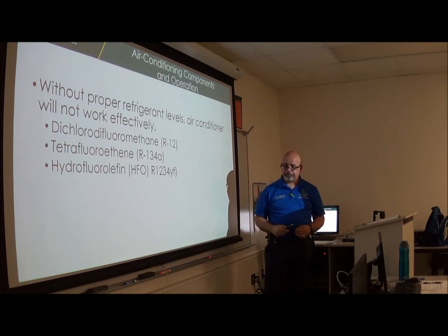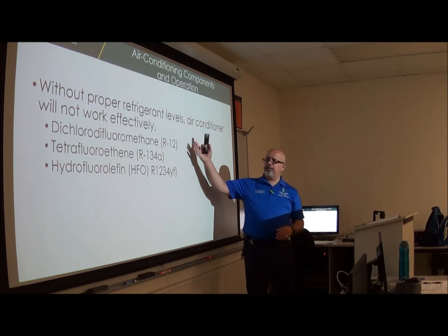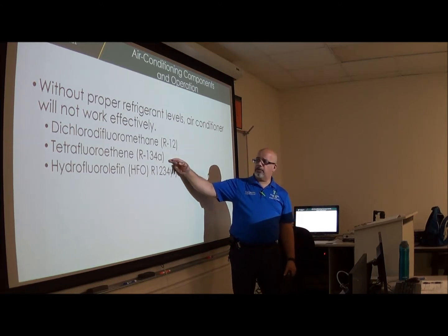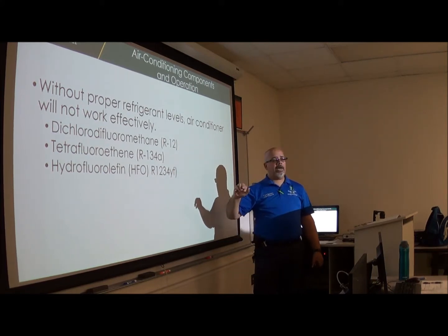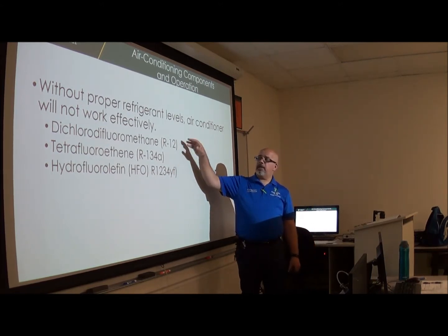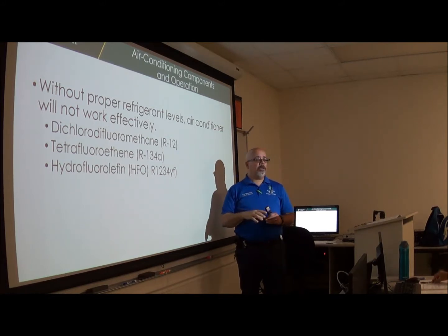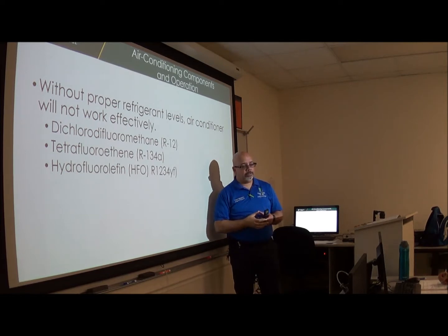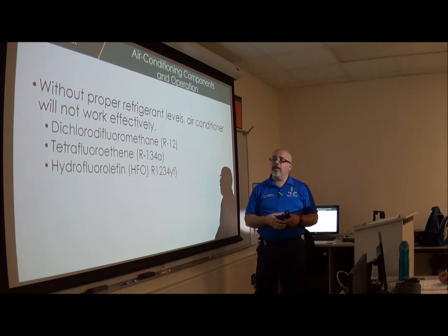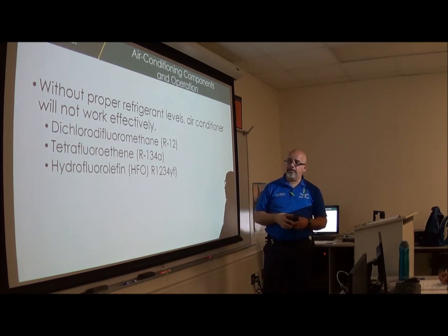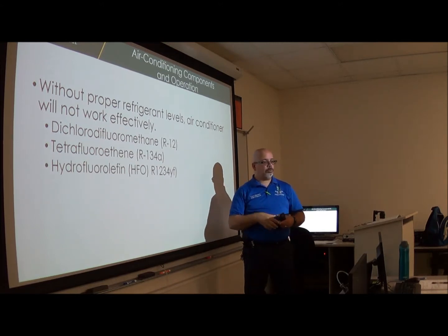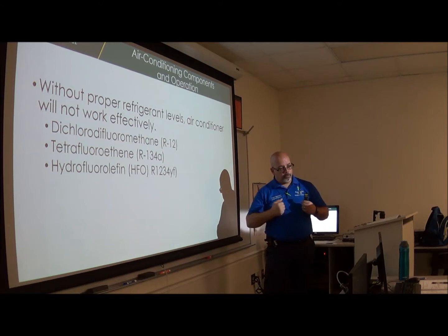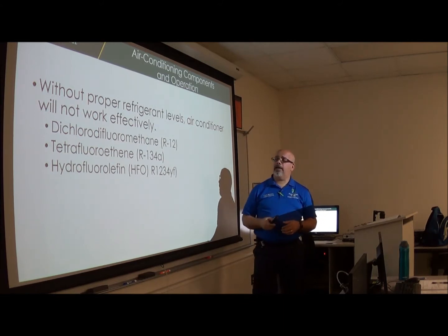There's a big difference between these three. When we changed from R12 to R134, all we had to do was take out the R12, open all the systems, and change the O-rings, which were black at that time, for green ones, which are the ones for R134A, because they hold more pressure than the black ones.